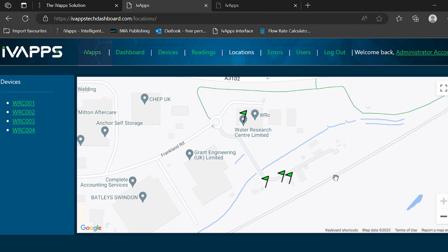For example, within the test loop setup that we have here, if number 1 is running green, number 2 has hit a trigger level, let's assume it's gone amber, well, is number 3 seeing that same problem, or is number 3 recovering, suggesting that there's a very localized problem near number 2? Or conversely, if number 2 is amber, is number 3 in fact gone red, suggesting that there's a problem that is very much getting worse as you get to the back end of the network.